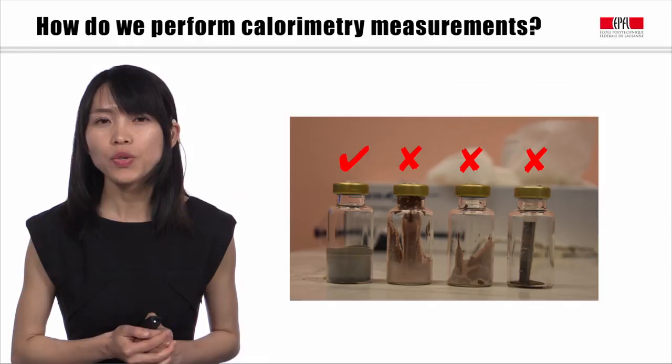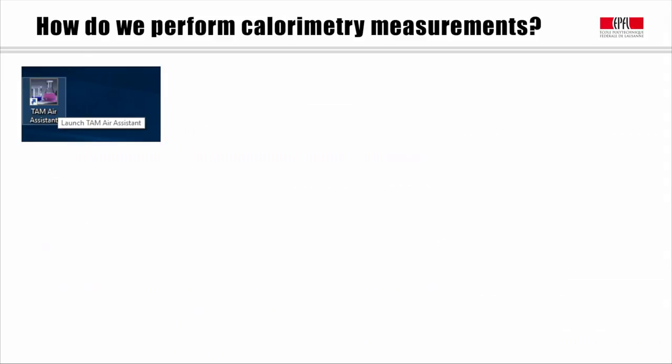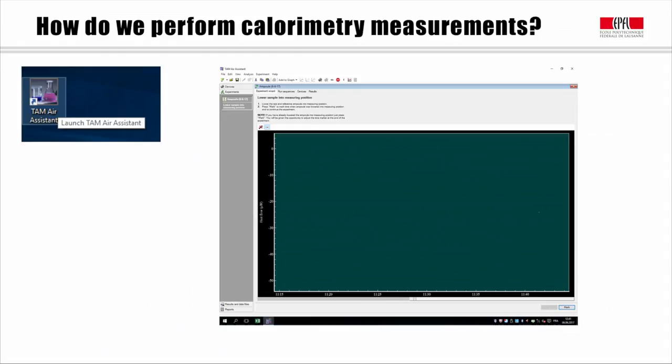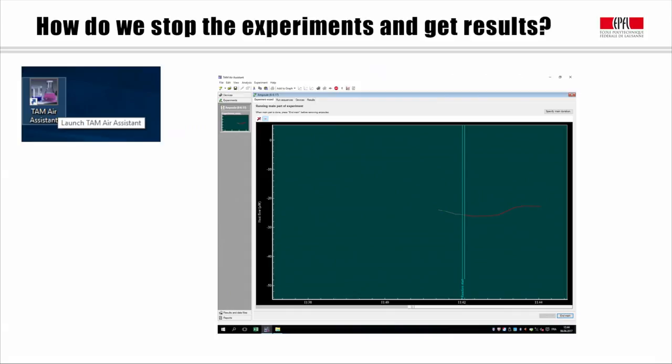Now our experiment is going on. We can use the experimental wizard to check how the experiment is going. When the experiment finished, we need to do the final baseline. Principally, it is the same as the initial baseline and there is another wizard that will guide you for all the steps. Just remember, before you do the baseline, you need to take out the sample but leave the reference inside.